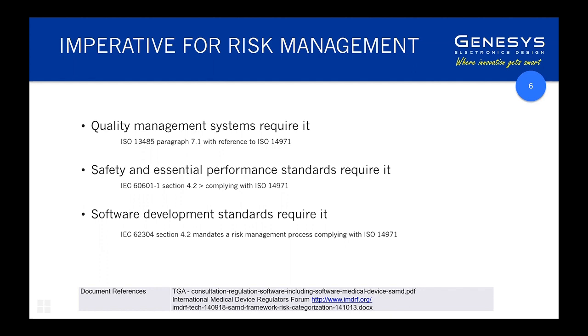When you look at IEC 60601-1, it mandates the use of compliance with ISO 14971 for risk management, and similarly IEC 62304 for software development mandates risk management complying with ISO 14971. So bottom line is ISO 14971 is the Bible for risk management within the context of medical device development and deployment.